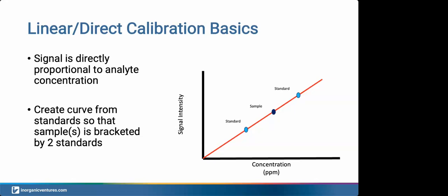For example, if a sample is suspected to have a concentration of 20 ppm, then the calibration curve should have a point higher, say 25 or 50 ppm, and a point lower, something like 10 ppm, to bracket the sample. The wide linear range of today's instruments allows users to create calibration curves over several orders of magnitude, which makes bracketing possible for nearly all applications.